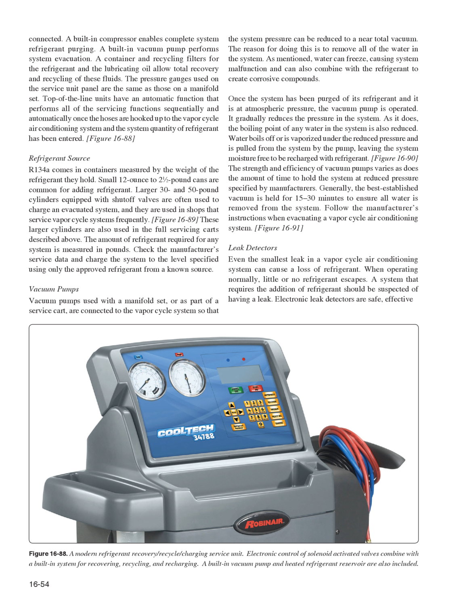Once the system has been purged of its refrigerant and it is at atmospheric pressure, the vacuum pump is operated. It gradually reduces the pressure in the system. As it does, the boiling point of any water in the system is also reduced. Water boils off or is vaporized under the reduced pressure and is pulled from the system by the pump, leaving the system moisture-free to be recharged with refrigerant.